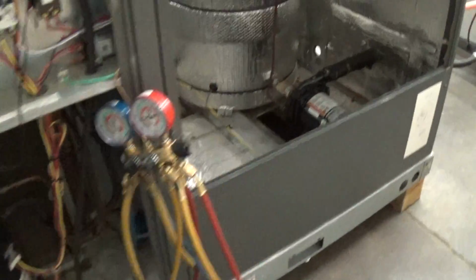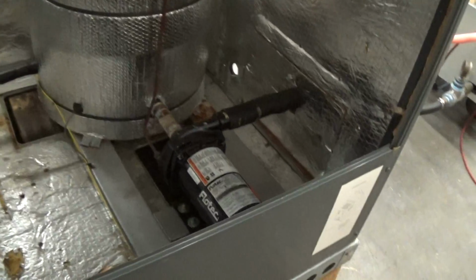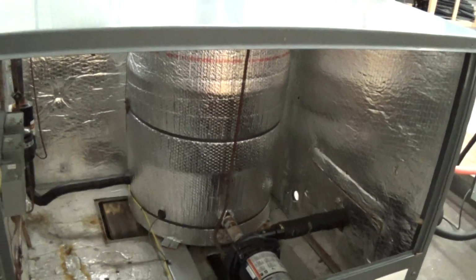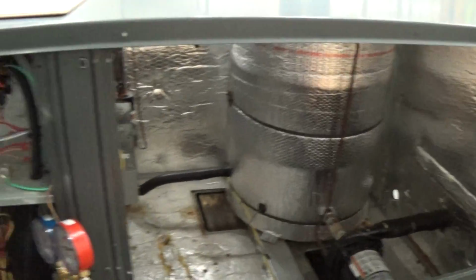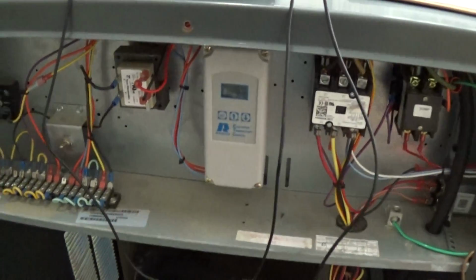We'll leave them off for the test because the way this one works is the condenser is all sealed here on this single fan system. And with the side covers off, that does not affect the airflow through the condenser. We like these ChillKing chillers because of their simplicity, but also their reliability in their operation. Right now we have the water heated, if you will, up to 58. It's a nice simple Ranco controller.